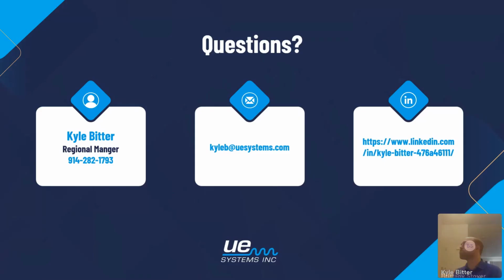When would you choose to use acoustic imaging versus traditional methods or procedures? Acoustic imaging serves very well for all of your airborne inspections, leak detection, and partial discharge detection. It can also spot bad mechanical assets. However, if I'm looking to establish a precision lubrication program, or I have steam traps and valves I want to test, the camera itself probably wouldn't be the best tool for that application. We want to make contact with those assets, whether it's a steam trap, bearing, or valve, to hear what's going on inside, since ultrasound won't penetrate solid objects. So think of the SI2 and SI1 acoustic imaging cameras as more for airborne applications, even though the Pro does have mechanical inspection capability, they're best served for airborne ultrasound.